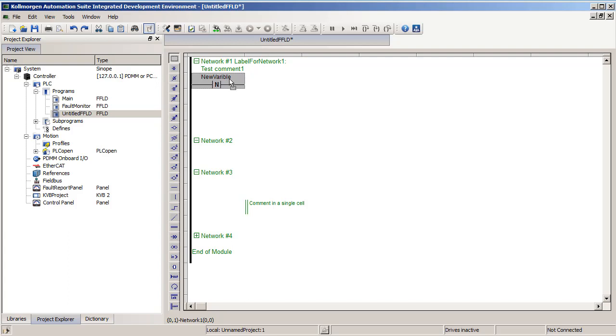We also have the N, or falling edge. This is also a pulse coil, but on the falling edge. So it will only allow power flow through when the variable goes from true to false. And then lastly we have the negation or NOT version of that. It will allow power to flow through all the time except when the variable inside of it has the falling edge, or was true in the previous scan, and is false in the next scan.